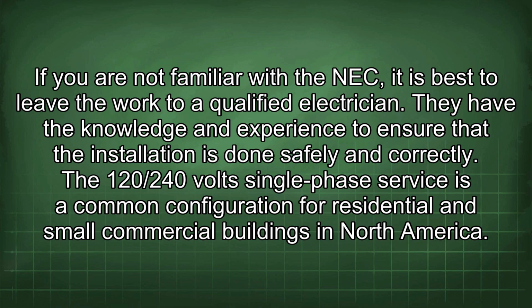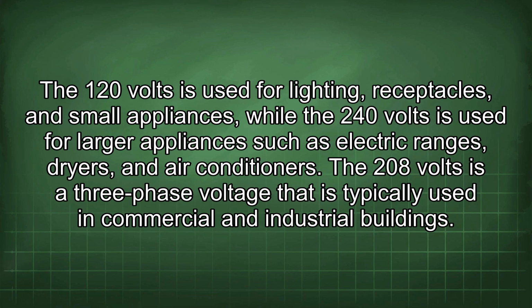The 120/240 volt single-phase service is a common configuration for residential and small commercial buildings in North America. The 120 volts is used for lighting, receptacles, and small appliances, while the 240 volts is used for larger appliances such as electric ranges, dryers, and air conditioners. The 208 volts is a three-phase voltage that is typically used in commercial and industrial buildings.